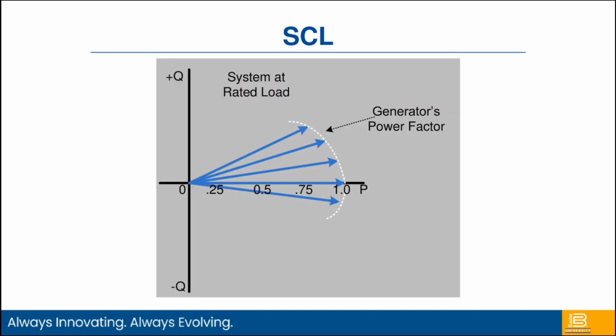And then the third type of limiter is our SCL, or stator current limiter, which is really looking at the output of the generator. So it's looking at stator current, or the output current of the machine. So I can set a total limit of current to limit the amount of excitation, at least, that I can push out of that particular machine, to make sure I'm not damaging or overloading the machine. So that is what the stator current limit does.